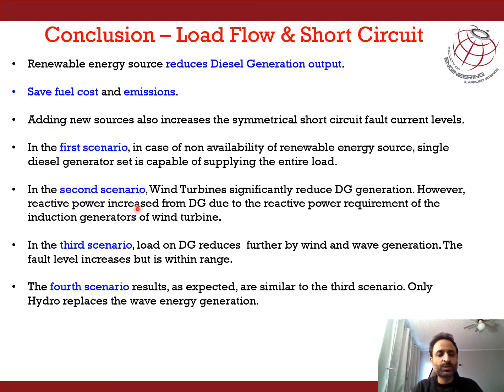In the second scenario, we indicated that the load on the DG sets can be almost halved by using the wind turbines. However, we will need the diesel generator to provide the reactive power. As a result, the reactive power in scenario 2 increases as compared to the first scenario.